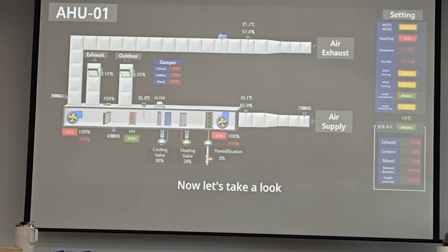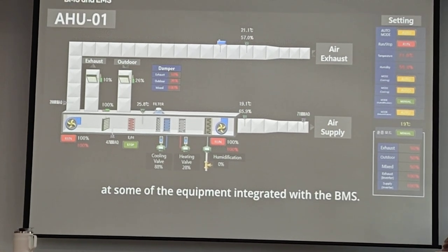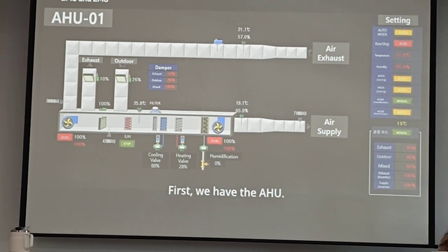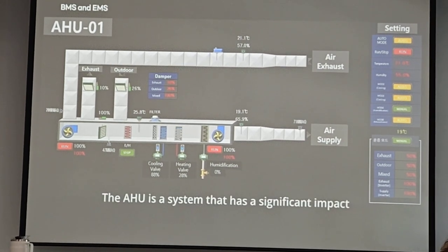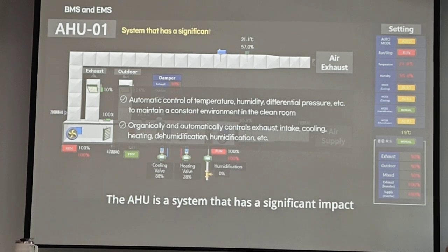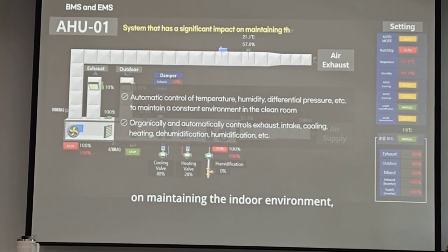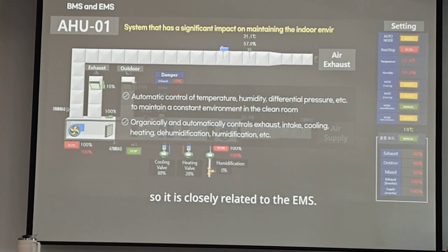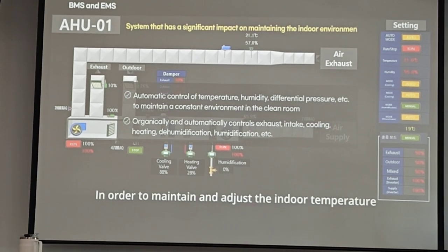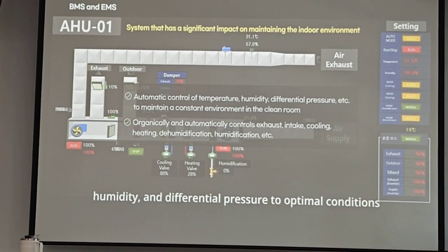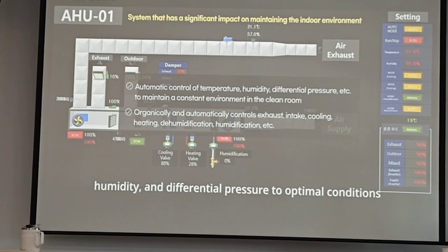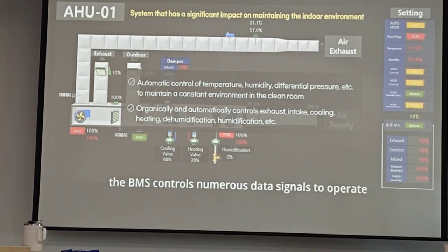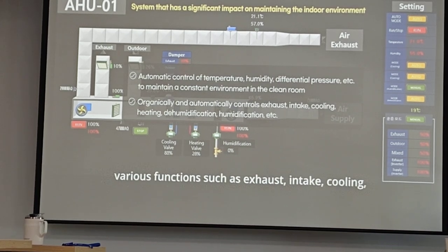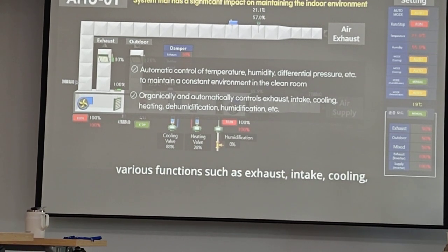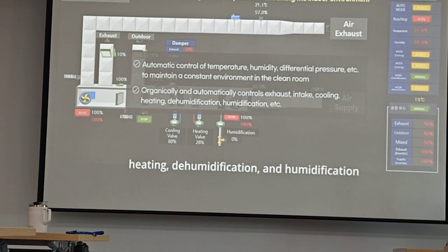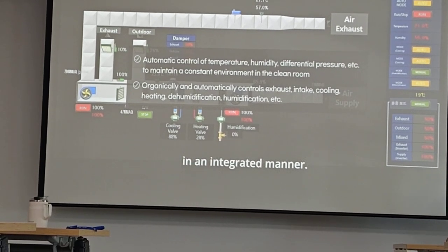Now, let's take a look at some of the equipment integrated with the BMS. First, we have the AHU. The AHU is a system that has a significant impact on maintaining the indoor environment, so it is closely related to the EMS. In order to maintain and adjust the indoor temperature, humidity, and differential pressure to optimal conditions, the BMS controls numerous data signals to operate various functions such as exhaust, intake, cooling, heating, dehumidification, and humidification in an integrated manner.